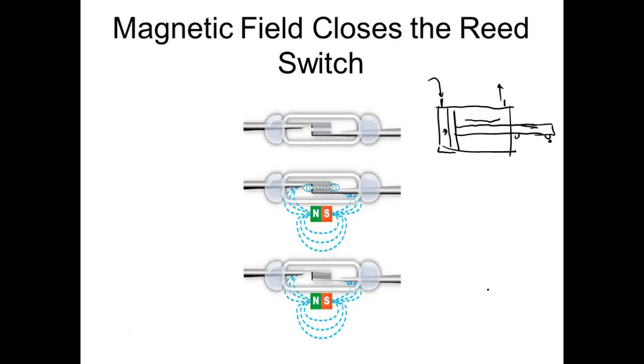Well, what's nice about pneumatics is that sometimes we can use plastic, and a lot of times they're made out of aluminum. Aluminum is non-ferrous, so a magnetic field will pass right through it. So on just about all your pneumatic cylinders, there's a magnet attached to the piston. Now I can put a sensor right here and a sensor right here, let's bring the pipes up this way. Then what can I do? You can tell when it's fully extended or fully retracted.